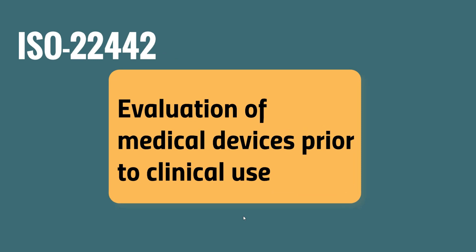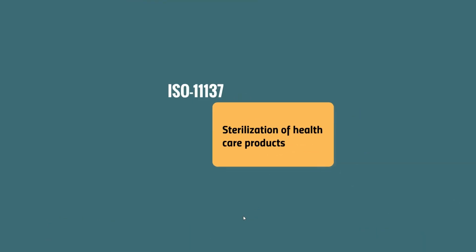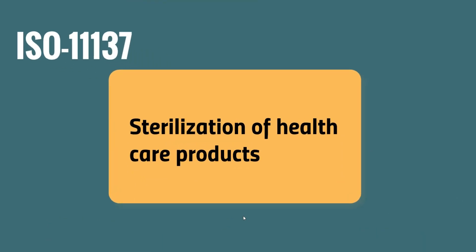15. ISO 11137 — this is the standard for the sterilization of health care products. This standard specifies requirements for the development, validation, and routine control of a radiation sterilization process for medical devices.